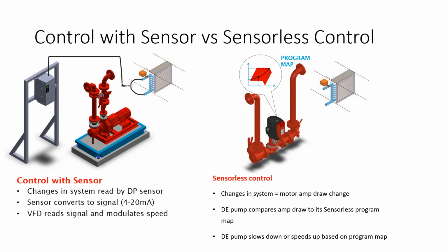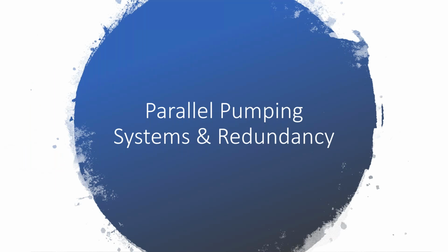The VFD reads that signal and will modulate the speed. A sensorless control actually senses the changes in the system by a motor amp draw change. The design envelope pump compares the amp draw to its programming map, which was predetermined at the factory, and then it slows down or speeds up based on the programming map to optimize the efficiency and maintain the head level of your system, which will in turn give you higher efficiency.